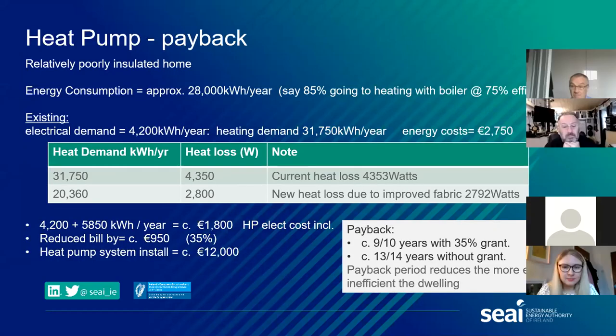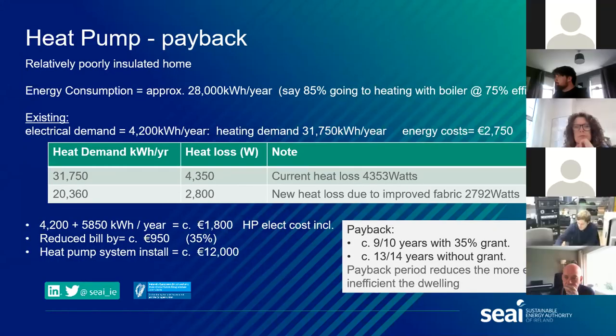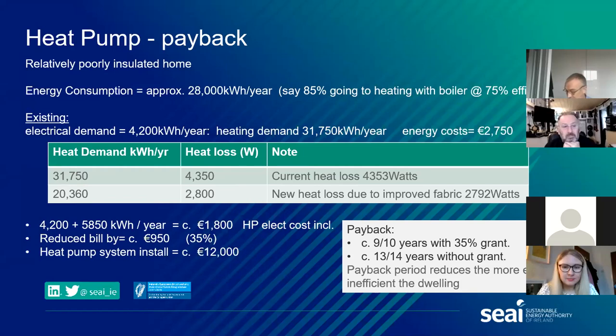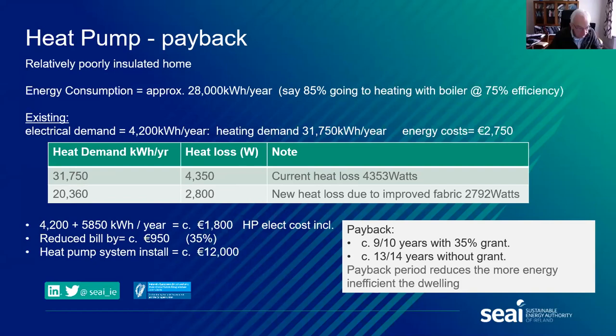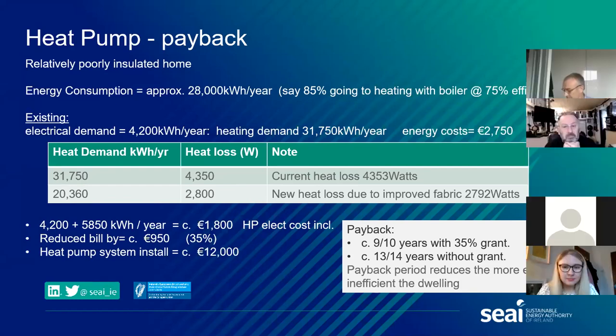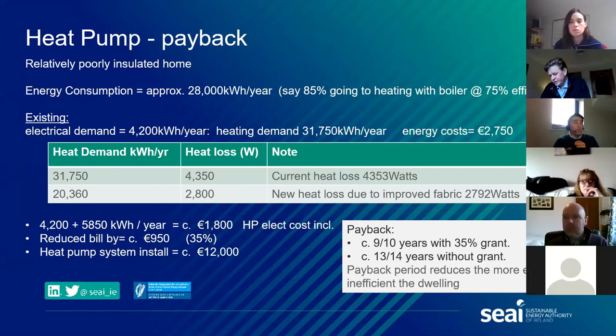But singling out the heat pump side of things, if I looked at a relatively poorly insulated home, their energy consumption would be in the order of 28,000 to 30,000 kilowatt hours per year with a boiler efficiency of 75%, and say 85% of that going towards heating. So you could be looking at an existing energy usage of about 36,000 kilowatt hours per year, giving an energy cost of 2,800.